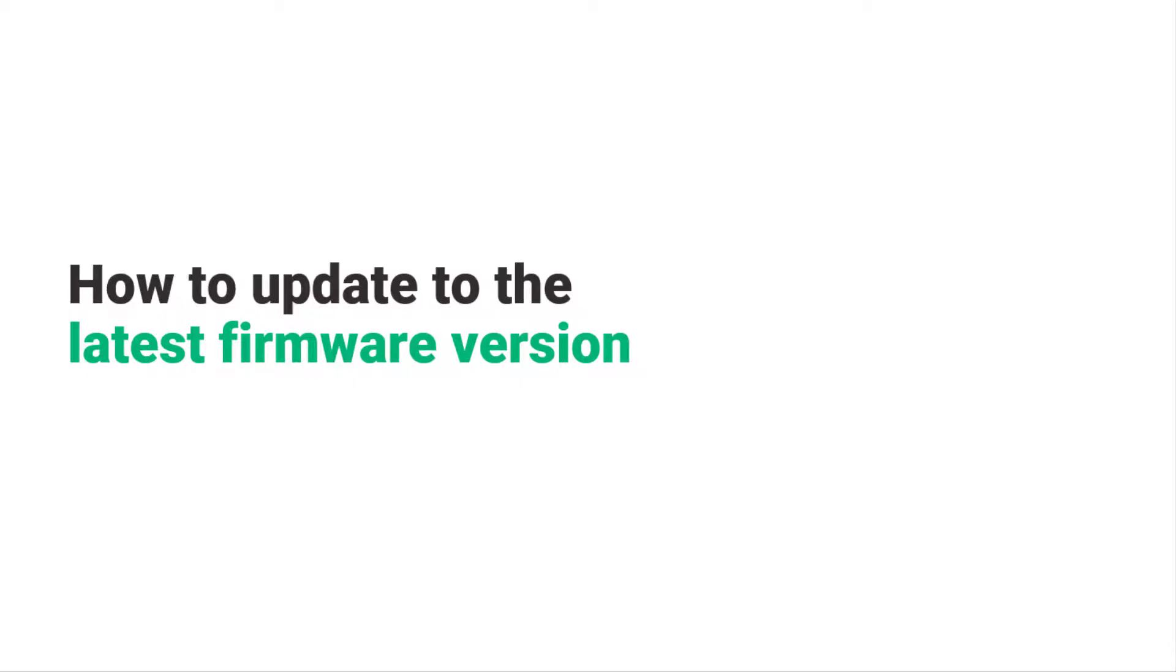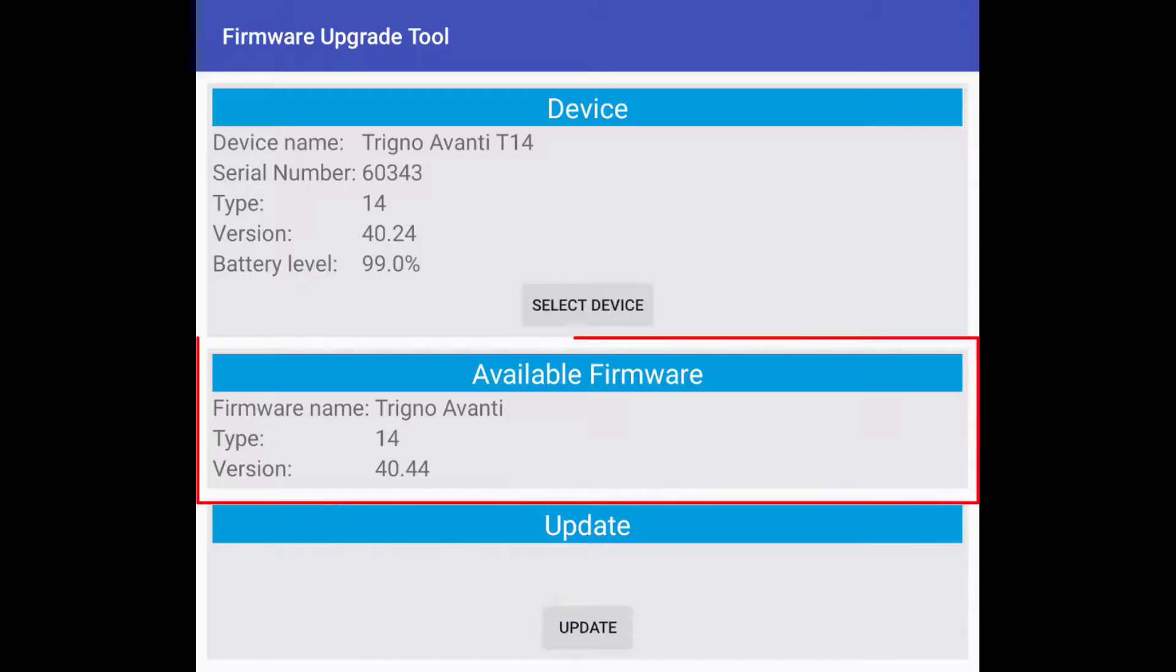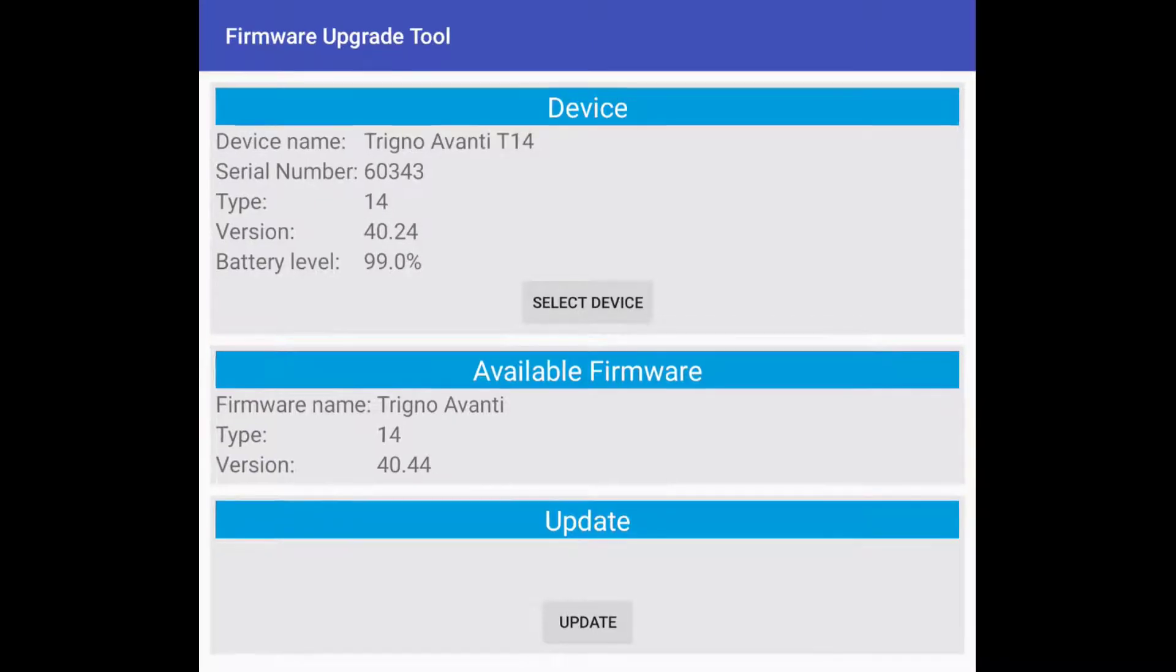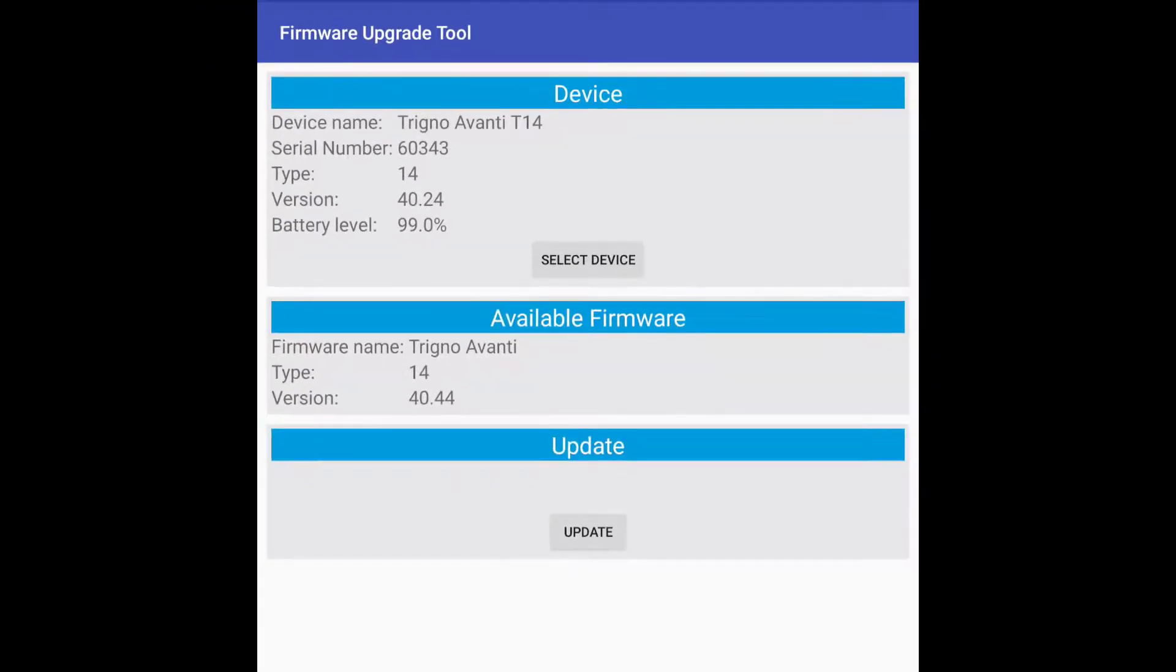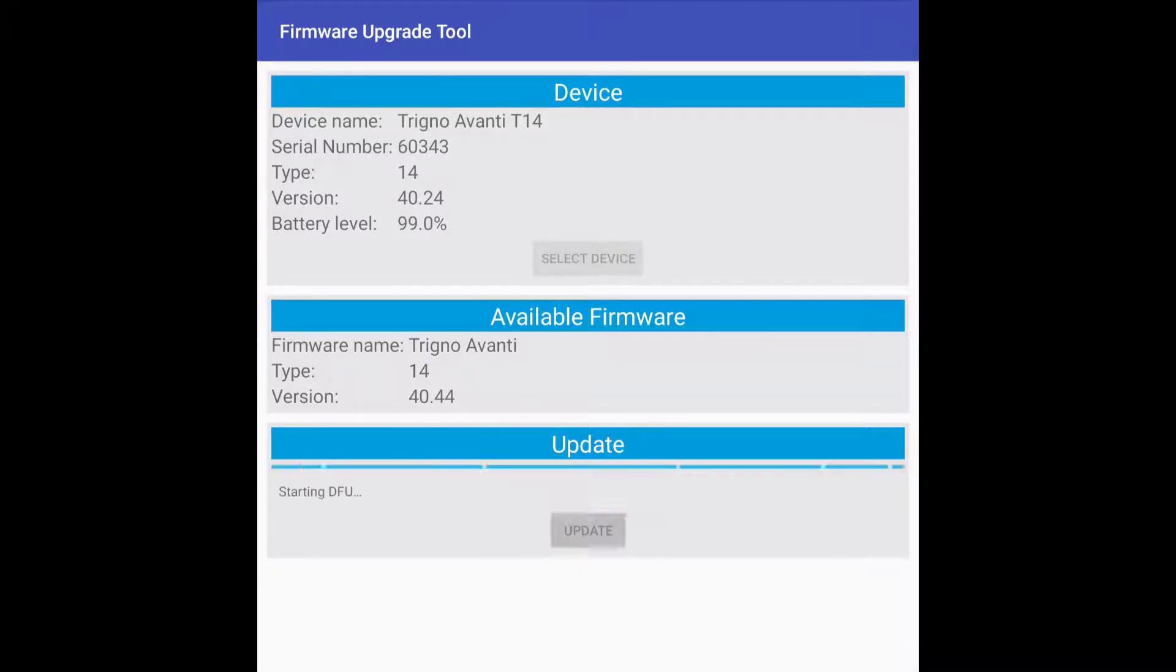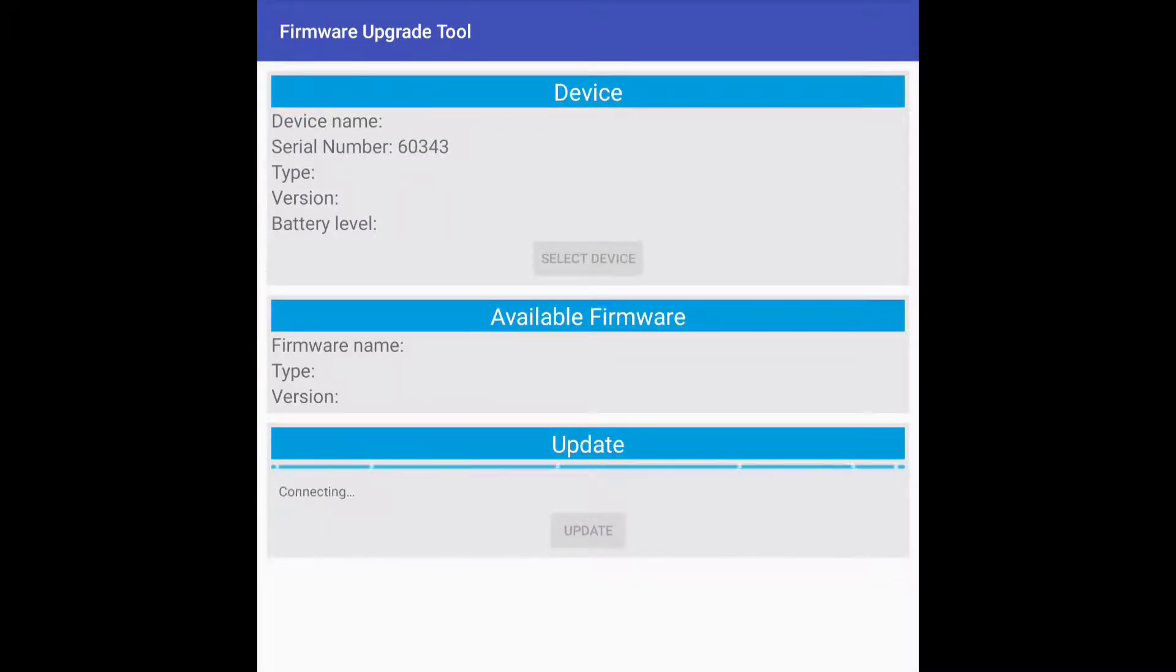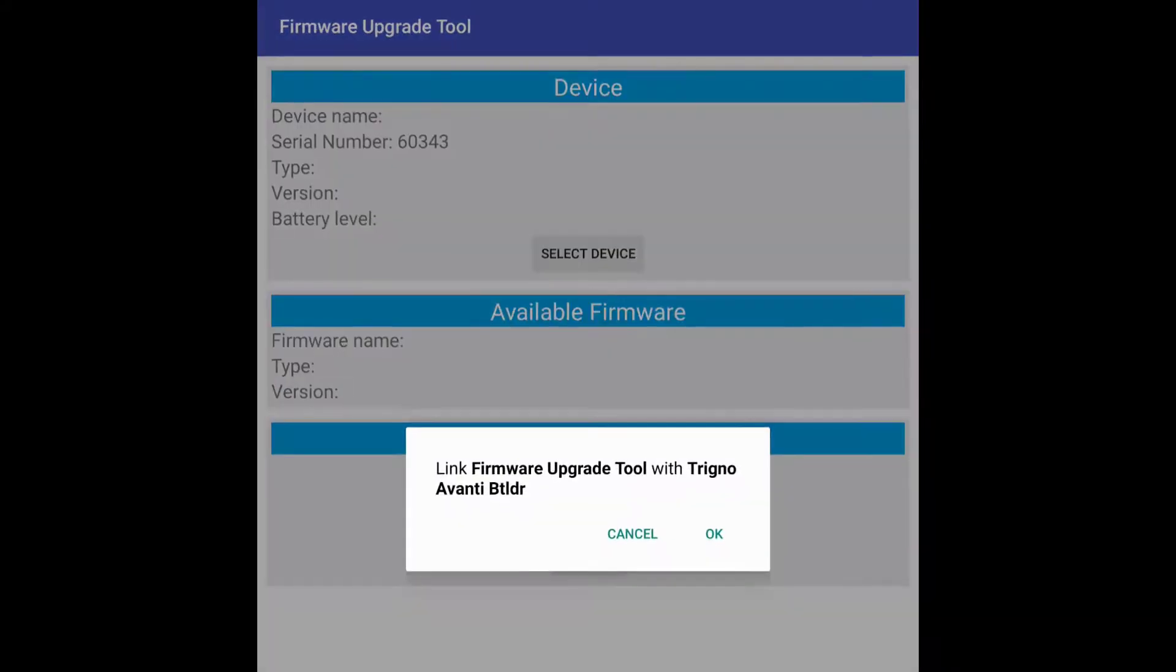To update to the latest firmware version, the available firmware box will show the latest firmware version the sensor can update to. Select the update button to update the sensor to the displayed firmware version. Click OK to link the firmware update tool with Trigno Avanti bootloader.